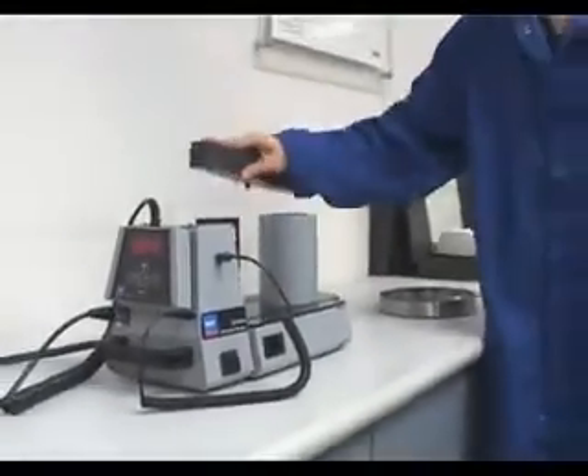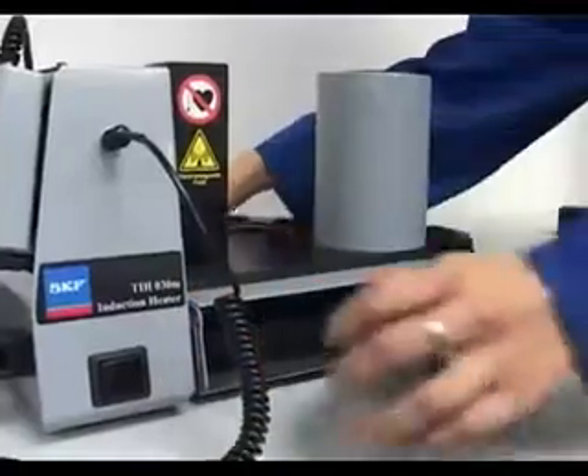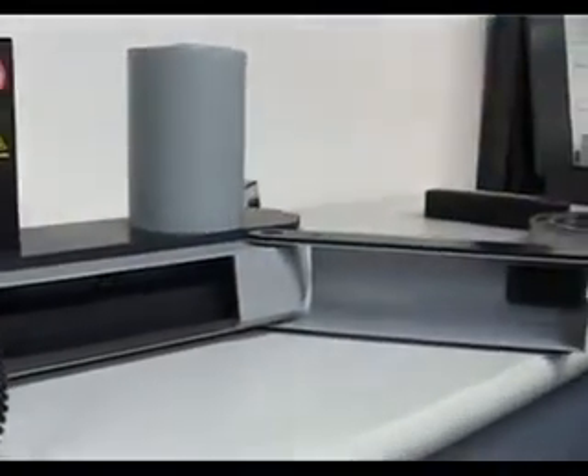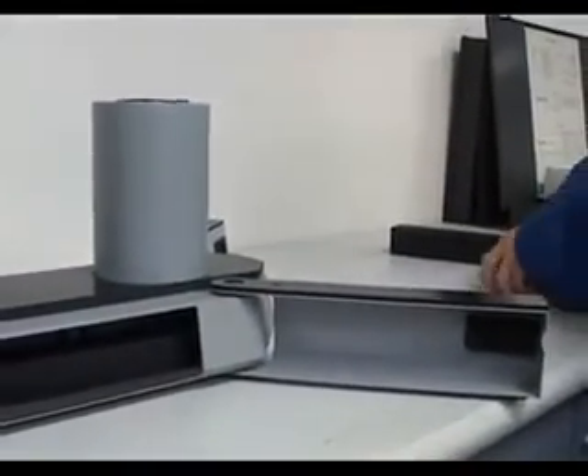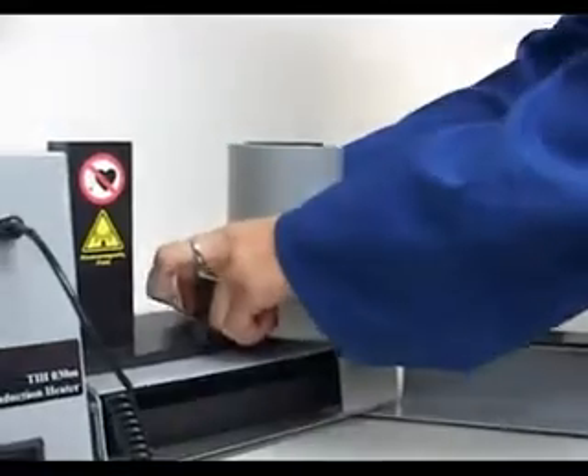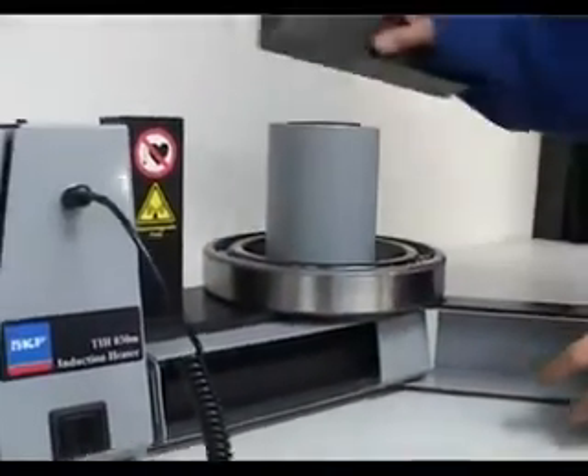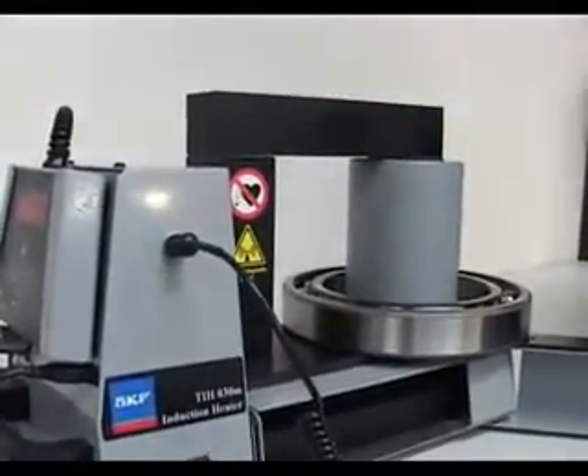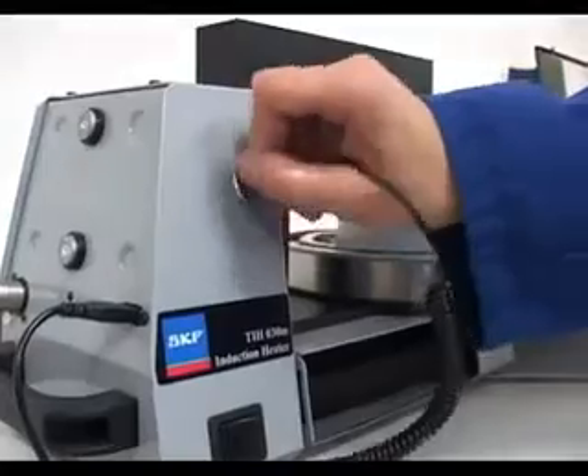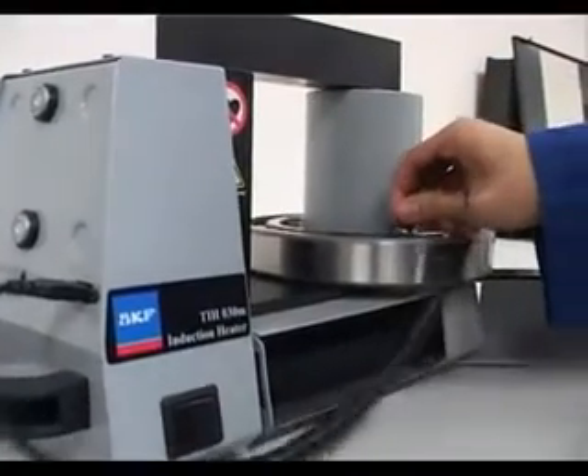First, remove the yoke and fold out the legs. Position the bearing to be heated around the coil. Carefully replace the yoke on the uprights. Finally, attach the temperature probe to the inner ring of the bearing.